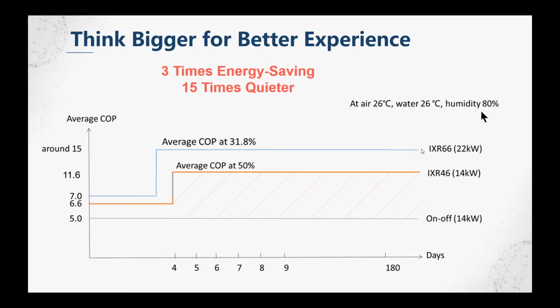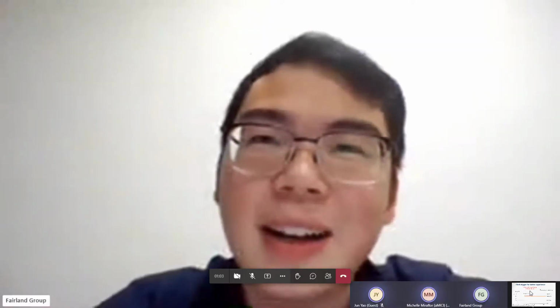When the humidity increases by 10%, the COP will go up by 4%. Okay, so we have a chart, we have a graph we test, but if used for simple calculation, you can also use this rule. It's also okay, but this working condition is approved by all players in the industry, 26-26-80. It's also the most common working condition in the heat pump industry.